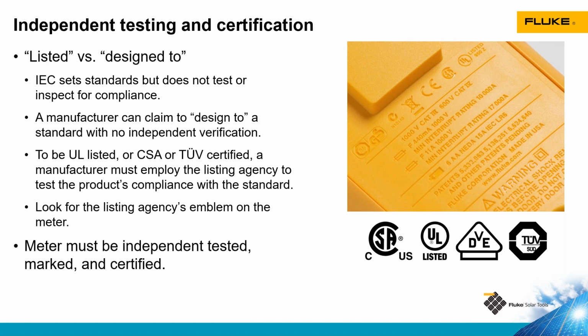When a tool is tested to a certain standard, the symbol of the testing agency will be stamped right in the case of the tool. We will typically use an organization like CSA or UL or TUV to do that type of testing. Not having that independent testing, you kind of never know what you're going to get if it hasn't been third-party tested.